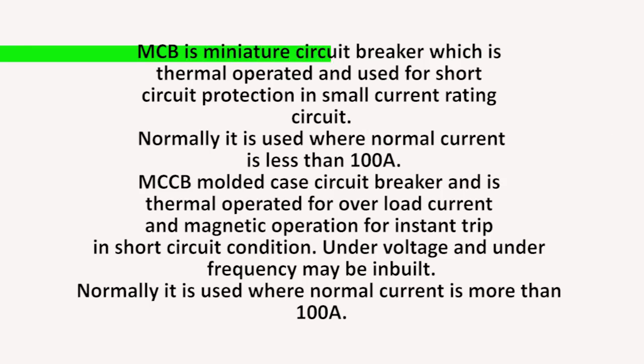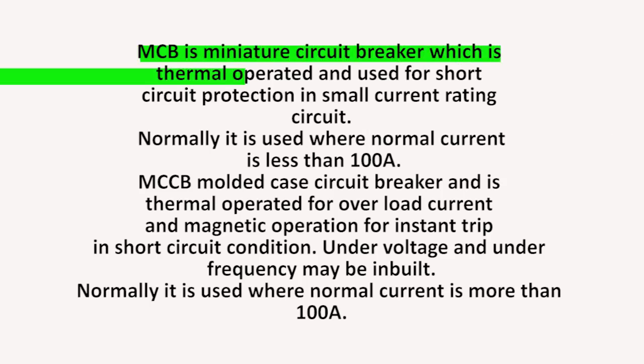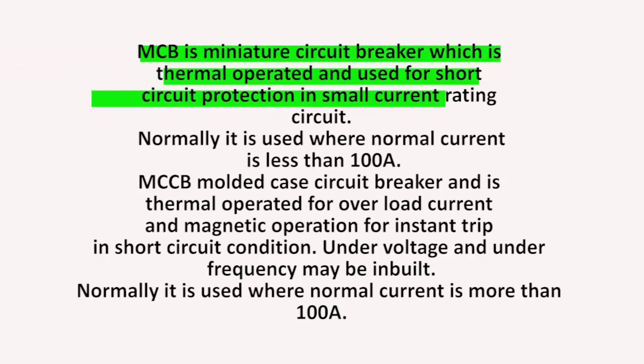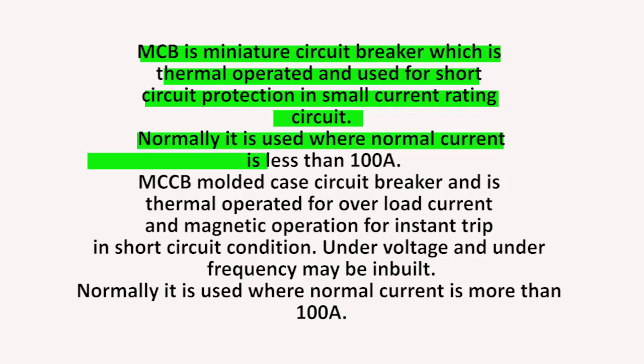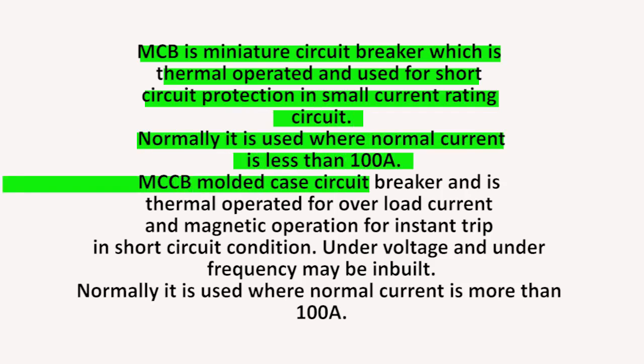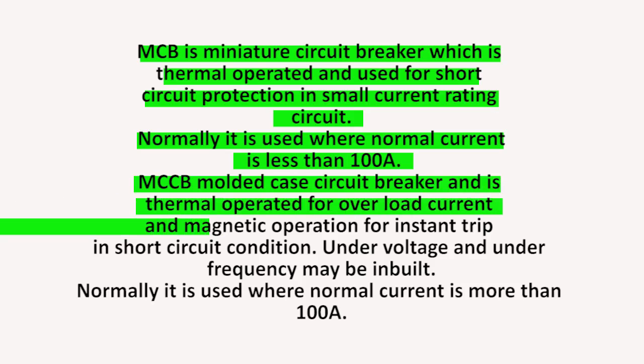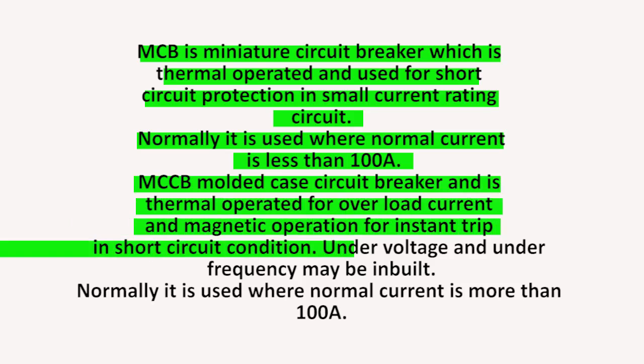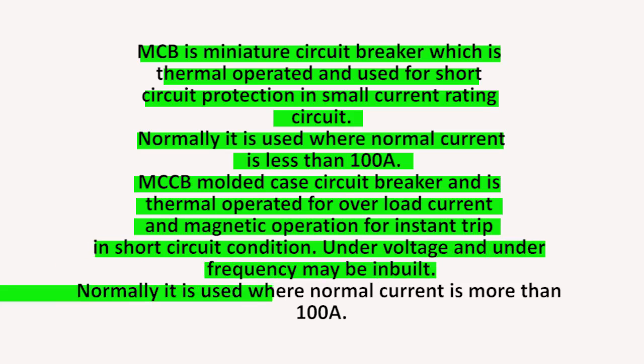MCB is a miniature circuit breaker which is thermal operated and used for short circuit protection in small current rating circuits. Normally it is used where normal current is less than 100 amps. MCCB is a molded case circuit breaker and is thermal operated for overload current and magnetic operation for instant trip in short circuit condition. Under voltage and under frequency may be inbuilt. Normally it is used where normal current is more than 100 amps.